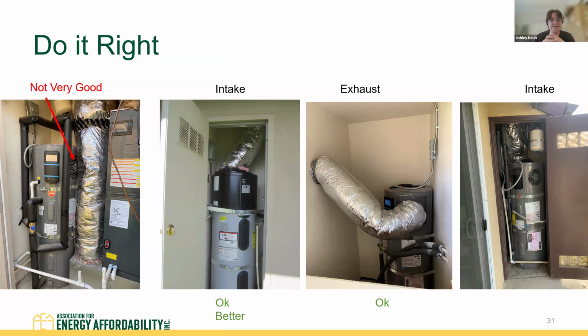If you are going to duct, it's important to make sure that the ductwork is nice and straight, that it's as short of a run as possible with as few bends as possible, and usually with at least an 8-inch diameter. Like you can see, this second picture from the left is a pretty good example of a fairly straight intake duct without too many bends. Same with the picture on the far right, another example of a pretty straight intake duct, whereas that one in the middle is a little more restricted. It's going to impact the performance more. Next slide.